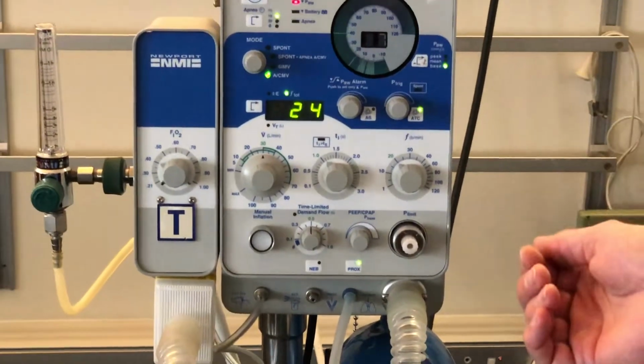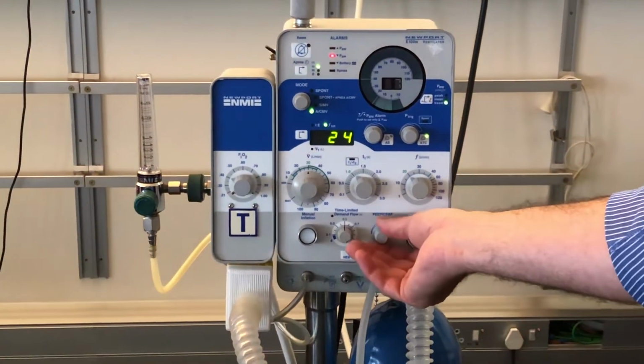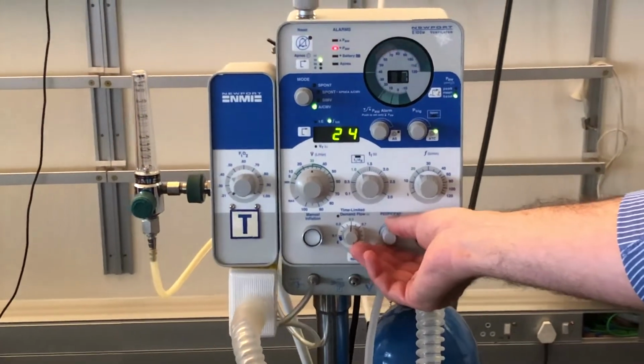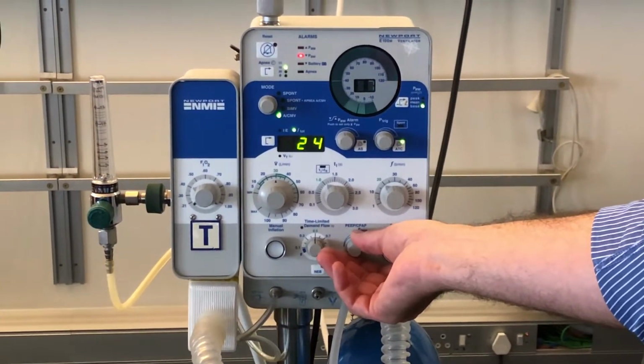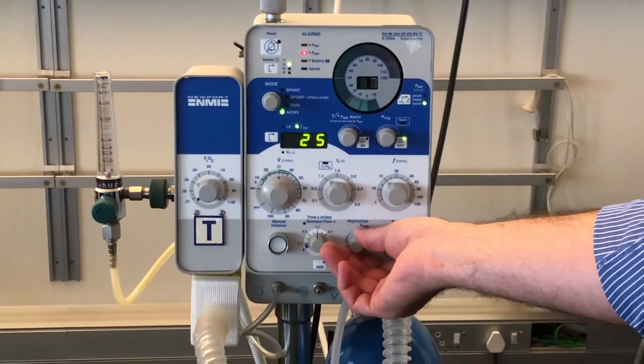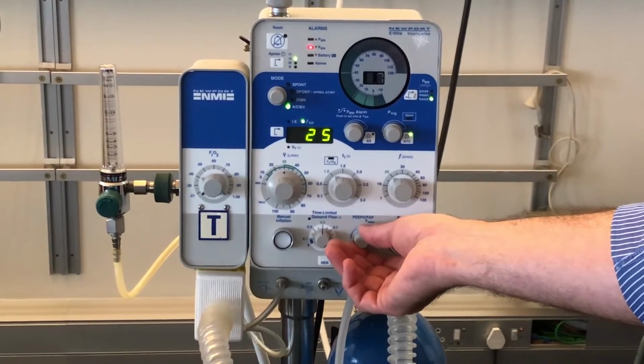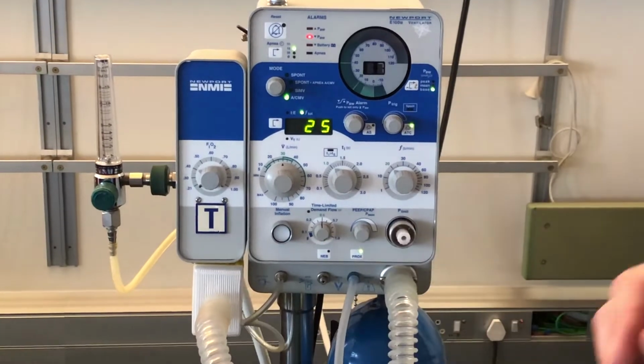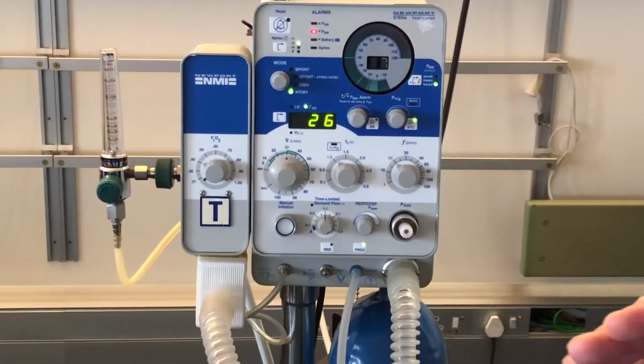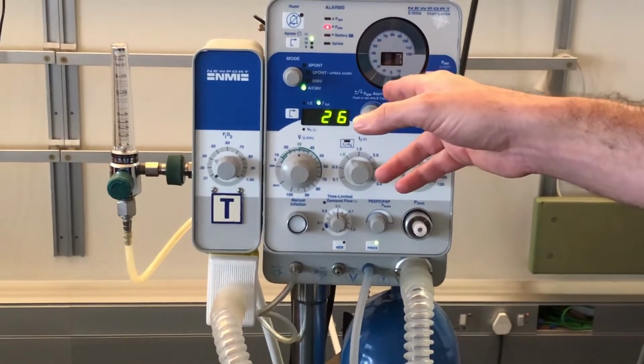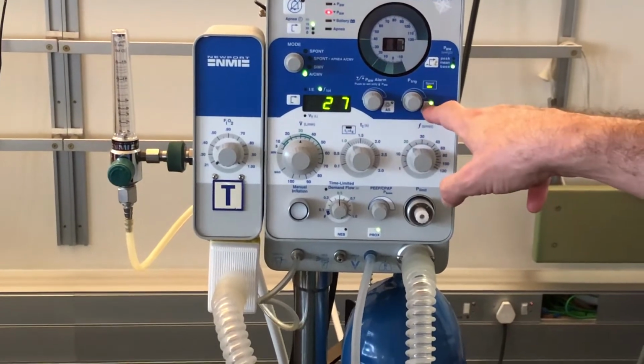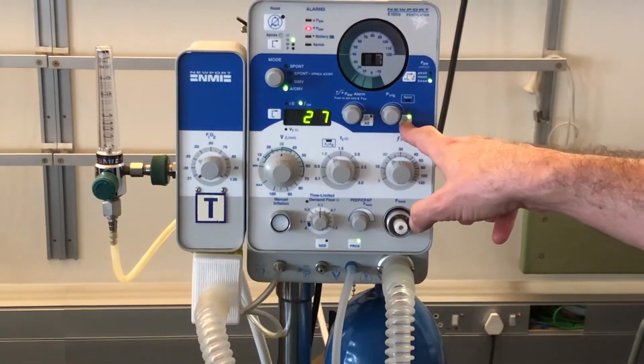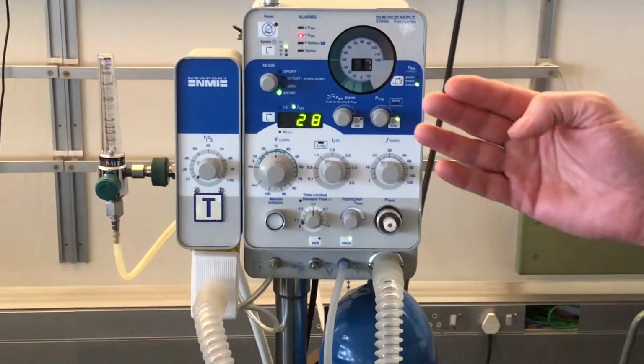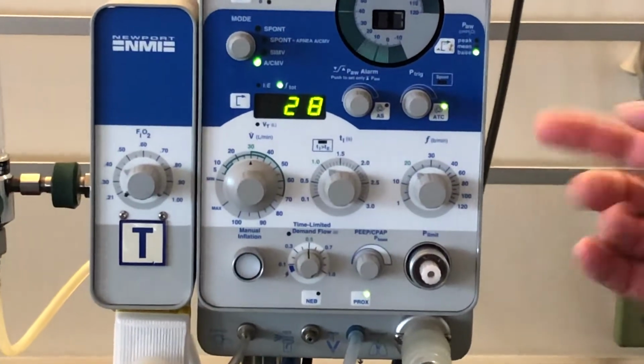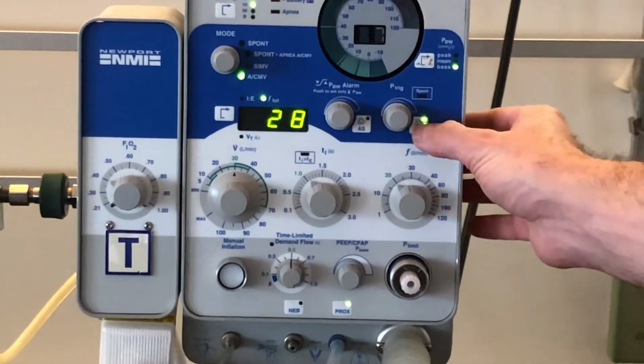So I've increased the PEEP setting now. You'll see it's on 7. I'm going to make it 8. And you'll notice that an interesting phenomenon has started to take place. And that is the machine is auto-triggering. The reason the machine is auto-triggering is I haven't gone and adjusted the trigger setting. So with the PEEP being higher, the patient is meeting the criteria for a trigger with every breath.